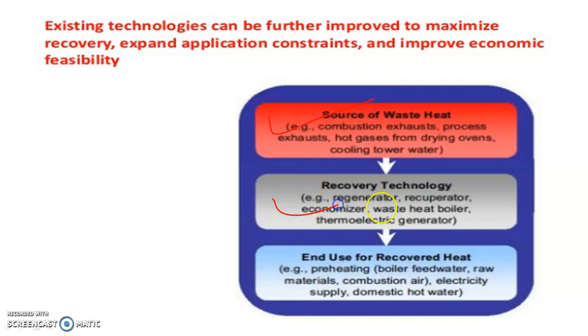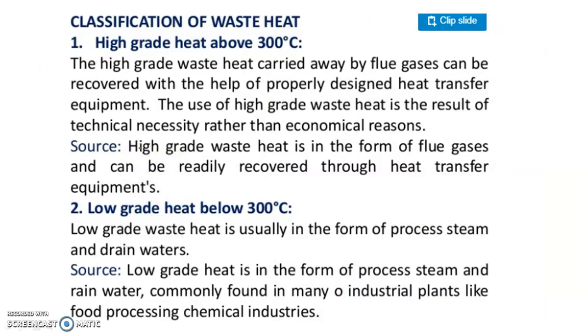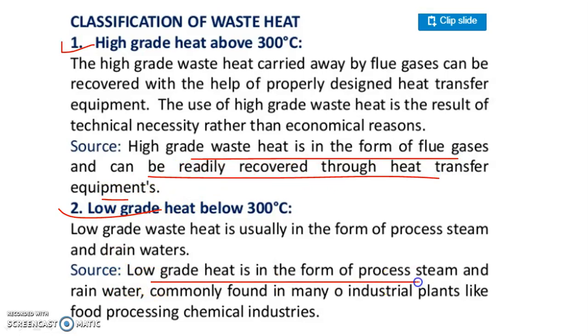Recovery technologies and equipment used are regenerator, recuperator, economizer, waste heat boiler, and thermoelectric generator. The last one is the end use for recovered heat, which is preheating of boiler feed water, raw materials, combustion air, electricity supply, and domestic hot water. Classification of waste heat: high grade heat above 300 degrees centigrade and low grade heat below 300 degrees centigrade. High grade waste heat is in the form of flue gases and can be readily recovered through heat transfer equipment, while low grade heat is in the form of process steam and rainwater, commonly found in many industrial plants like food processing and chemical industries.